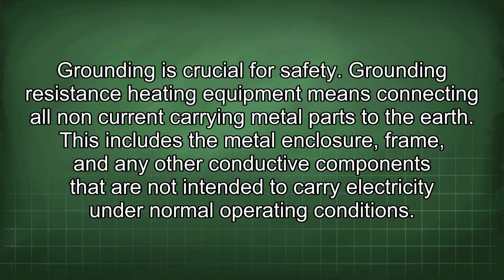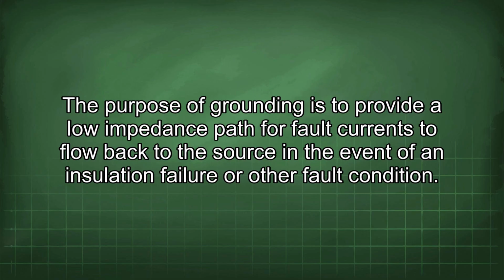Grounding is crucial for safety. Grounding resistance heating equipment means connecting all non-current carrying metal parts to the earth. This includes the metal enclosure, frame, and any other conductive components that are not intended to carry electricity under normal operating conditions. The purpose of grounding is to provide a low impedance path for fault currents to flow back to the source in the event of an insulation failure or other fault condition.